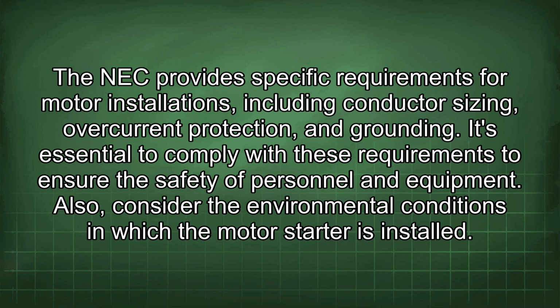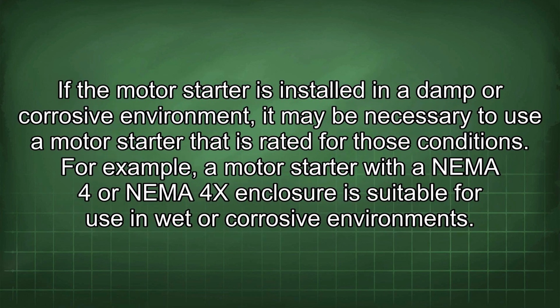Also, consider the environmental conditions in which the motor starter is installed. If the motor starter is installed in a damp or corrosive environment, it may be necessary to use a motor starter that is rated for those conditions. For example, a motor starter with a NEMA 4 or NEMA 4X enclosure is suitable for use in wet or corrosive environments.